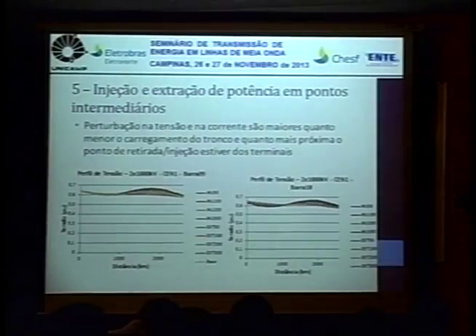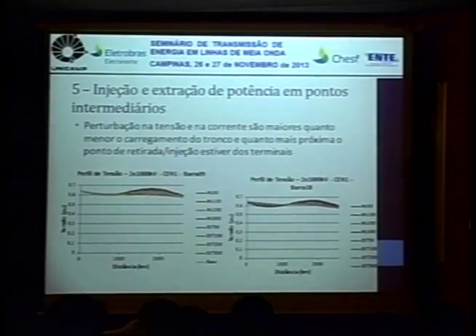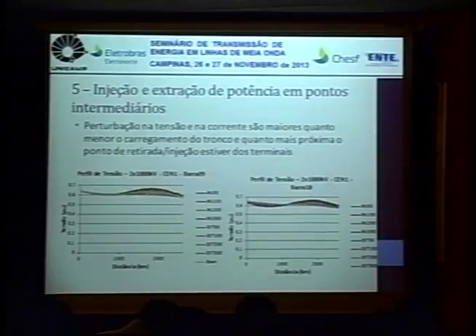The line is optimized. We did the optimization by changing taps and phase shifters, adjusting the reference power we wanted. And then we do this extraction from 50 to 300 megawatts at 1/4 of the line. This is the change in the voltage profile. It was not big for this power range we are extracting.